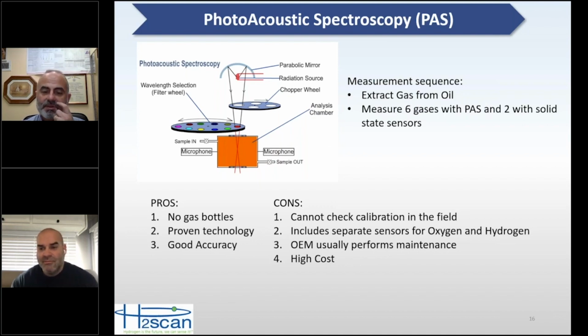So for photoacoustics, if you're doing the 8 diagnostic gases, or now some people are having up to 10 gases, you do have separate solid state sensors generally for oxygen and hydrogen. And typically on these, it's a fairly complex system, so the OEMs usually perform the maintenance, but I understand some OEMs are now allowing and training their customers to do the maintenance. And there is a high initial cost for the photoacoustics. Again, any of the 8 gas monitors are much more complex and have a lot more parts, so they do tend to be significantly more expensive than, say, just a hydrogen monitor.